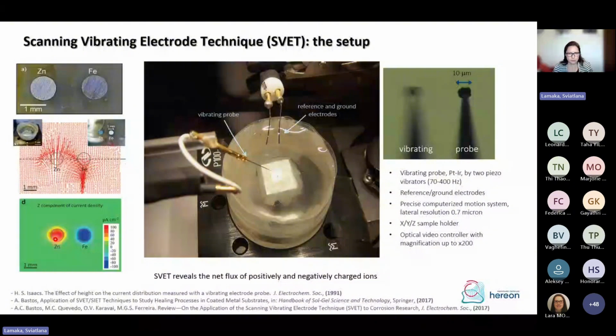And we grow a layer of platinum black. The diameter of the probe is between 10 to maybe 20 micrometers, and the vibration amplitude is also between 10 to 20, maybe 30 micrometers, but not more than that. And so the vibrating probe of SVET, during this vibration between 2 points near the metal surface, measures the potential difference that is formed in solution due to the ionic fluxes produced on the sample surface by chemical or electrochemical reaction. And then the relationship between this measured potential difference and the associated current density is established by calibration.